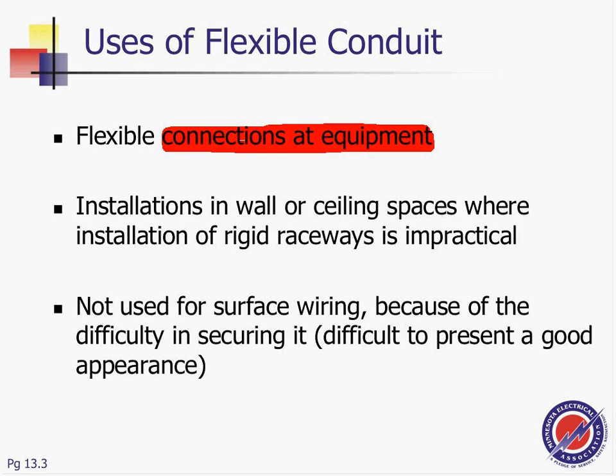So connection to equipment, very interesting. Use in wall or ceiling spaces where installation of rigid raceways is impractical. So basically, if I am to put a number one use of flex, it is really connecting to equipment. So equipment could be an air handling unit. Because of vibration, here's my big air handling unit right in here. Here's my disconnect over here. I bring my EMT right in here. And then after I get my EMT, I bring my Liquidtight flexible conduit and tie it to my air handling unit.